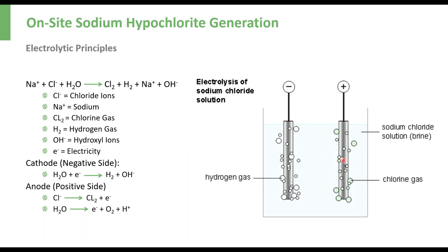So within this beaker, let's say we wanted to make an equivalent pound of chlorine. That equivalent pound of chlorine would take a 24-hour period within this beaker configuration. So the hydrogen that's bubbling over that 24-hour period, we would be seeing 1/35th pound. The hydrogen is being produced at such a low rate that it's not really that hazardous. Now, that does not mean you do not need to take safety into consideration, because hydrogen is an explosive, highly flammable gas. As long as you respect it, that is an area that you do not have to worry about, but you have to respect it.